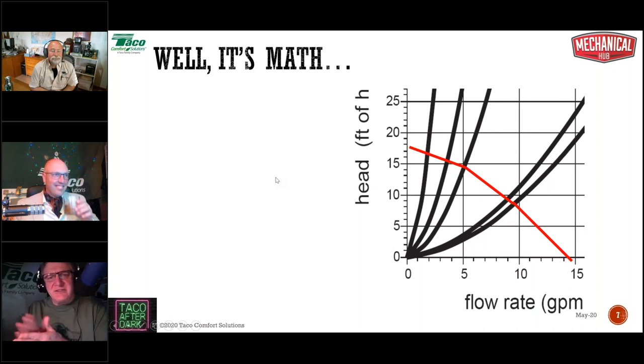All righty. So why does the delta T shrink incredibly so? It's the math. The math kind of says it has to. You don't get around that. And again, you don't have to do this math. Just understand that it exists. What I'm showing here is a typical three-speed circulator set to contractor, no callback motor, the Taco 008 single speed, whichever one it is. We're in high speed. And those system curves, those five black lines, those are system curves. They represent different combinations of zones that are calling at a given point in time. And as you see, the lines will intersect the pump curve at different points, which is where the system will actually operate in terms of flow and in terms of head differential.